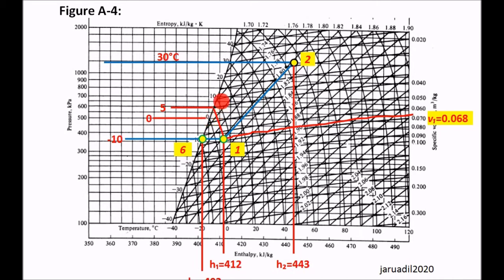You can see 0 degrees and 10 degrees. Since 5 is in the middle of 0 and 10, we estimate this point at 5 degrees Celsius. On the pH chart, constant temperature lines are drawn as curves — not straight down. Straight down means constant enthalpy. Constant temperature lines curve like this.